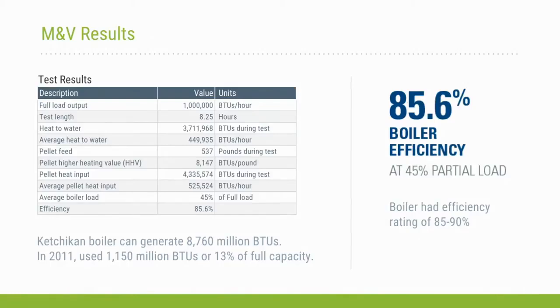One other comment, I showed at the bottom too, we talked about the boiler sizing. It was only running at 45% load at this point, but if you look at the total output that boiler is capable of during a year, it's only really 13% of its capacity. The heating load during the year, in other words, at Ketchikan, is only 13% of the heat that really could be put out by this boiler. So in essence, the boiler was fairly oversized. Next slide, please.